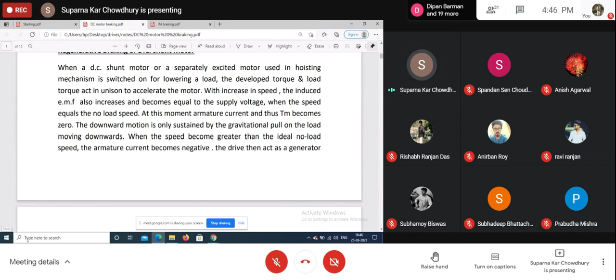With increase in speed, the induced EMF also increases and at a particular point becomes equal to the supply voltage, when the speed equals the no load speed. At this moment, the armature current and thus the motor torque becomes zero. Now, downwards motion is sustained due to the gravitational pull on the load. After this point, the speed becomes greater than the no load speed, and the armature current becomes negative. The drive then acts as a generator and feeds power back to the supply. And the torque will act as a braking torque. The motor attains a steady state speed when the braking torque developed is equal to the load torque.